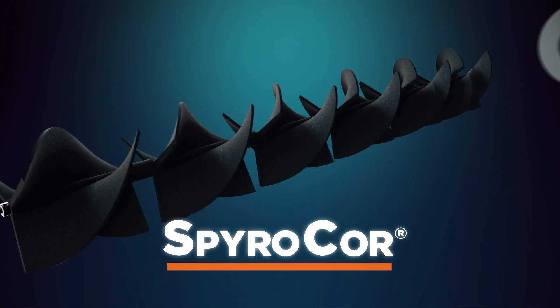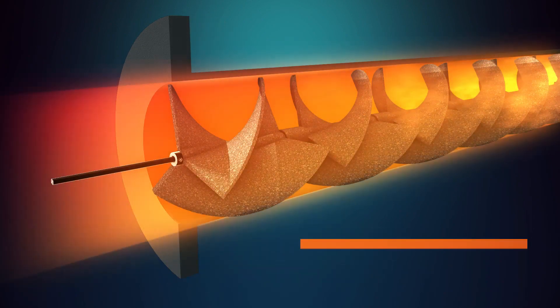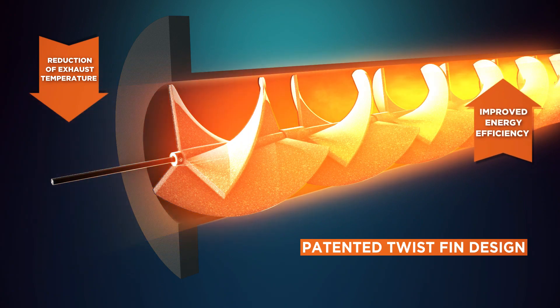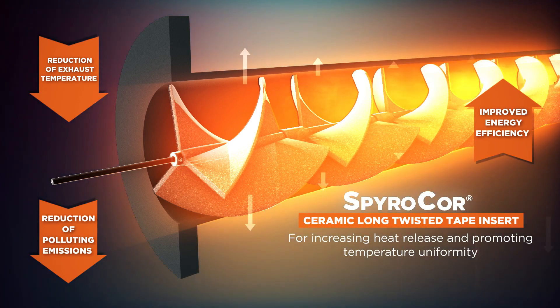SpyroCor inserts absorb the heat energy from hot exhaust gas that would usually escape and re-radiate the heat back into the furnace. The resulting reduction in exhaust heat temperature improves energy efficiency and reduces polluting emissions. Because the cold spots at the exhaust leg of the burner tube are eliminated, the temperature uniformity within the furnace is improved.